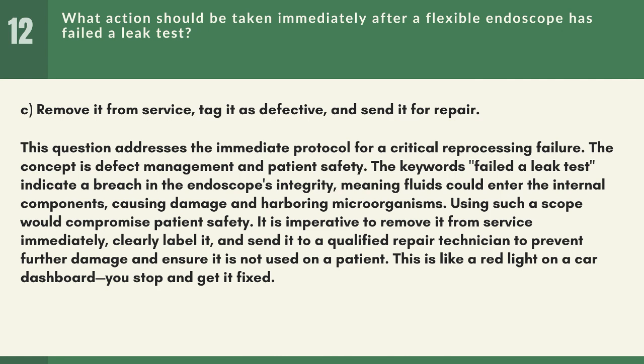This question addresses the immediate protocol for a critical reprocessing failure. The concept is defect management and patient safety. The keywords failed a leak test indicate a breach in the endoscope's integrity, meaning fluids could enter the internal components, causing damage and harboring microorganisms. Using such a scope would compromise patient safety. It is imperative to remove it from service immediately, clearly label it, and send it to a qualified repair technician to prevent further damage and ensure it is not used on a patient. This is like a red light on a car dashboard: you stop and get it fixed.